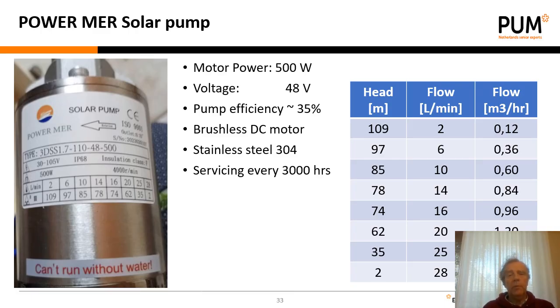With the pump from the factory comes a table that demonstrates, if you use the pump with a certain head, what the flow in liters per minute can be and what the flow can be in cubic meters per hour. So we have to consider the head of our application, and then we can see in this table what the expected flow will be.